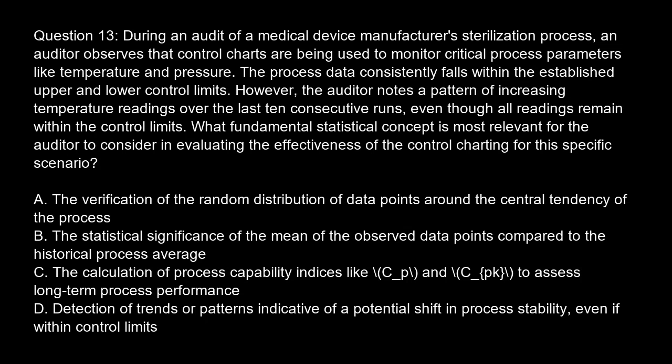Question 13. During an audit of a medical device manufacturer's sterilization process, an auditor observes that control charts are being used to monitor critical process parameters like temperature and pressure. The process data consistently falls within the established upper and lower control limits. However, the auditor notes a pattern of increasing temperature readings over the last 10 consecutive runs, even though all readings remain within the control limits.